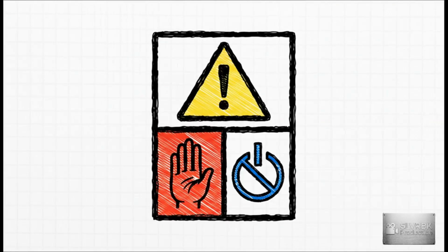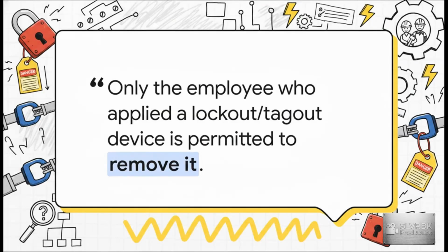To ensure maximum clarity and prevent any kind of catastrophic miscommunication, those tags also have to be highly legible with standardized formatting. The legends, the actual text on the tags, must offer clear, undeniable instructions. OSHA gives us specific examples for this. Do not start, do not open, do not close, do not energize, or do not operate. The wording simply leaves no room for interpretation. We're going to leave you with this absolute foundational rule of OSHA compliance. It states, only the employee who applied a lockout/tagout device is permitted to remove it. Now, yes, there are extreme, documented exceptions for emergencies, but this is the golden rule.